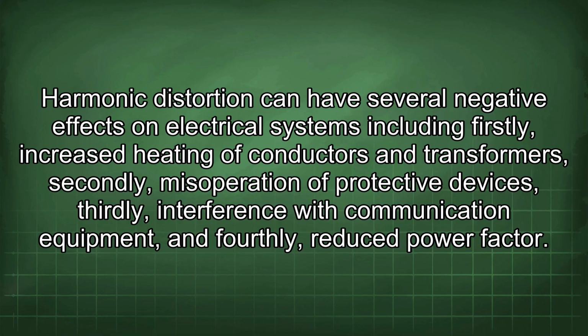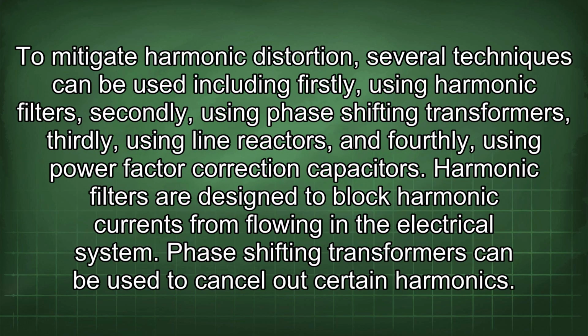Secondly, misoperation of protective devices. Thirdly, interference with communication equipment. And fourthly, reduced power factor. To mitigate harmonic distortion, several techniques can be used, including firstly, using harmonic filters. Secondly, using phase-shifting transformers. Thirdly, using line reactors. And fourthly, using power factor correction capacitors.